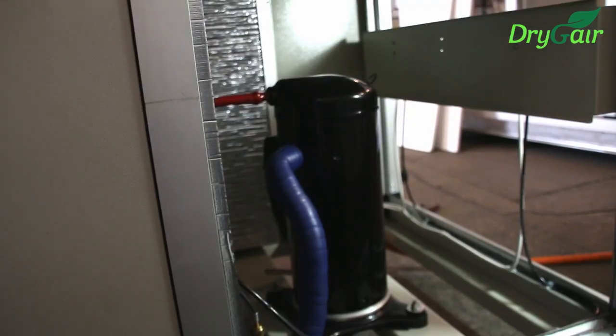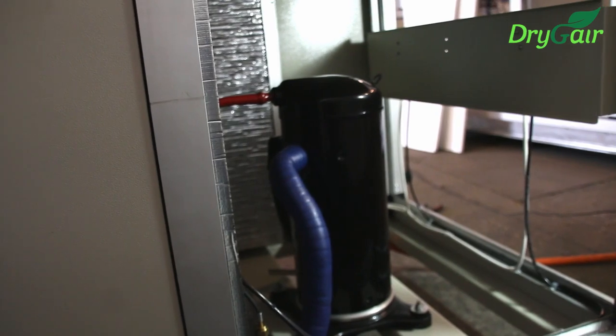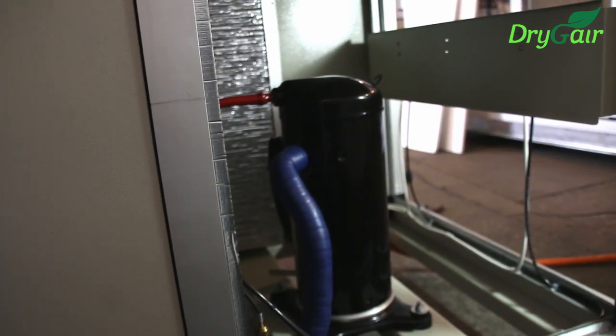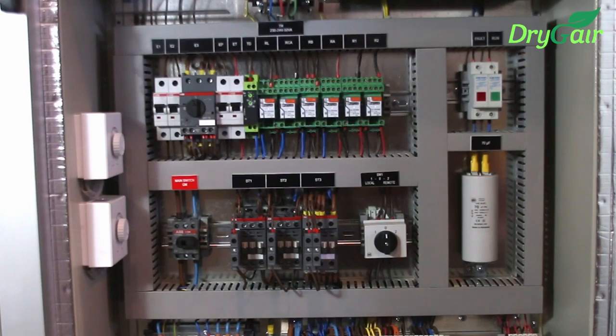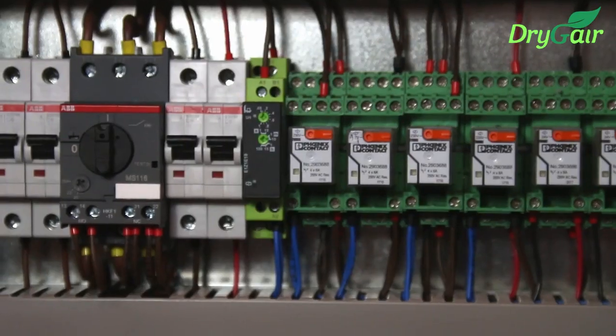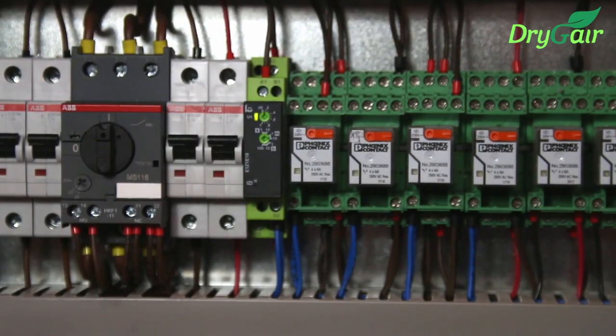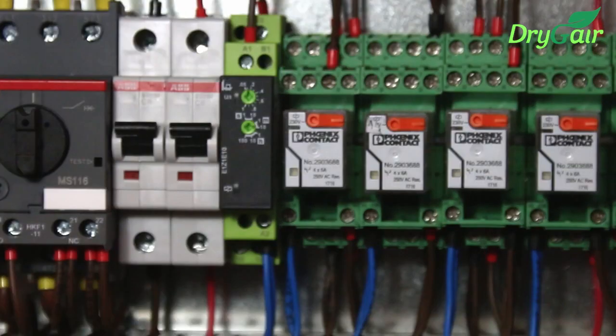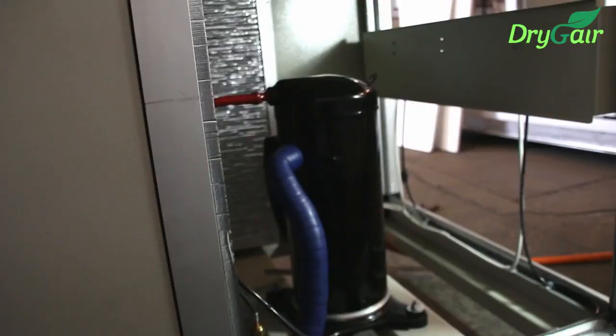Next, check to see that the compressor is operating. It should begin to work around 5 minutes after the machine is turned on. In the electric compartment, you will see a component labeled TD, time delay, which indicates the status of the compressor. A flashing green light means the timer is counting down. When both the green and yellow lights are on, the compressor is ready to start and is waiting for a command from the humidistat or climate control system to begin. When both lights are off, the compressor is on. You will be able to hear it running.